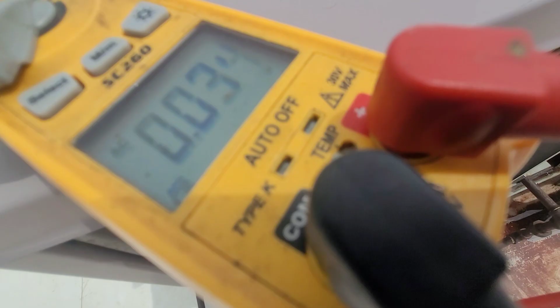But if I check from C to G, I'm getting 25 volts. And if I check from C to Y, we're getting 24 volts. C to W, we're getting nothing. And so this contactor is pulled in. Now when I unplug this blue wire, it drops the contactor. So we're getting 24 volts from our thermostat, as far as I can tell. See, when I plug that in, it fires up again. It is getting power from somewhere downstairs. But how? So I gotta go up, or down rather, and figure out where this thing is getting its power.